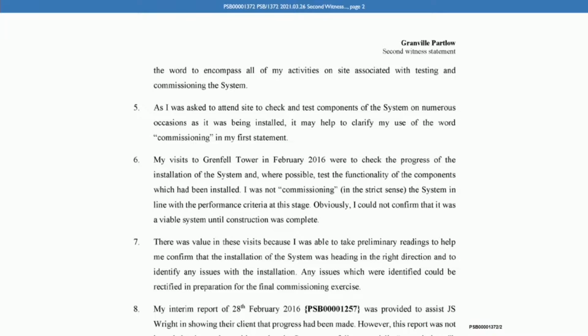And then at paragraph 6, you go on to say, my visits to Grenfell Tower in February 2016 were to check the progress of the installation of the system and, where possible, test the functionality of the components which had been installed. I was not commissioning in the strict sense the system in line with the performance criteria at this stage. Obviously, I could not confirm that it was a viable system until construction was complete. So there you have helpfully clarified that your visits in February were to check the progress of the installation and, where possible, check the functionality of installed components, but you were not at that stage commissioning the system. Is that correct? Yes, that's correct.